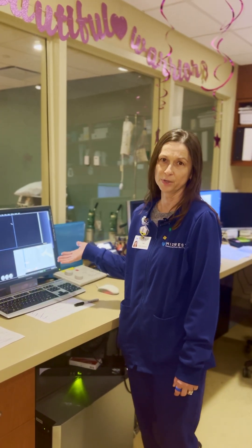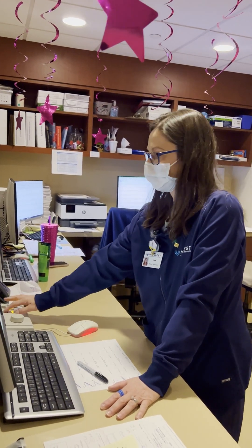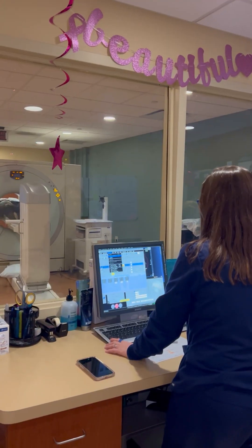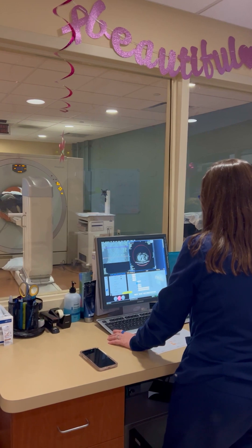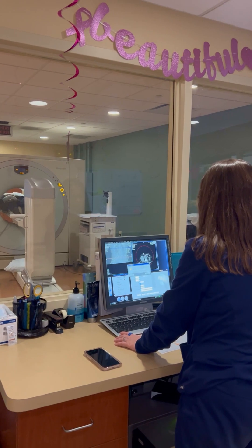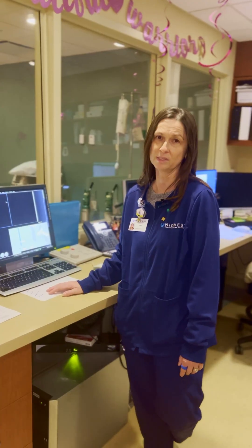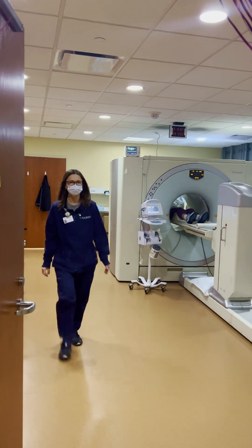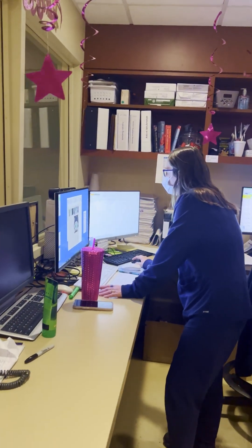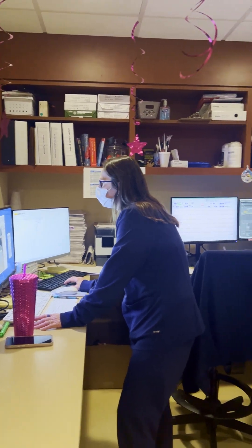This is the acquisition computer — this is how I acquire the pictures for the stress test. We first start off by doing a quick topogram, then we do the CT images for attenuation correction, and then we do the PET portion of the stress test. First I start the images, then I run back and start the generator to get the resting dose. After the eight minutes of pictures, we do the ten seconds of the medicine stress test. Then I come back, start the stress picture acquisition, run back to the generator, and get the second tracer for the images, followed by the last eight minutes of pictures.